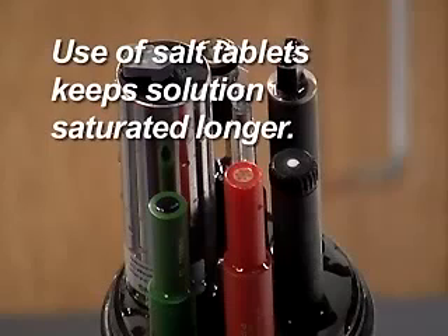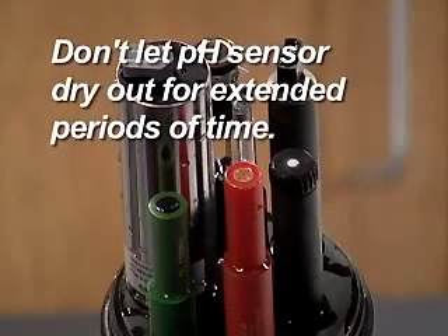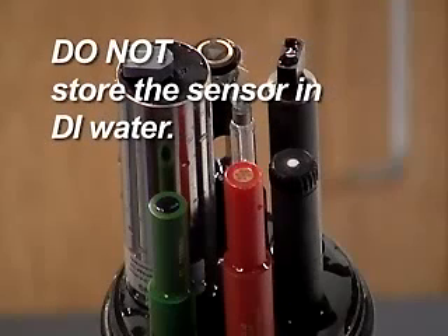Use of the salt tablets from the maintenance kit will keep the electrolyte solution saturated for longer periods of time. The pH sensor should not be allowed to dry out for extended periods. When not in use, store the sensor in pH 4 buffer or alternatively clean tap water. Do not store the sensor in deionized water or sample water. DI water will damage the sensor bulb, and the organisms in sample water will foul the bulb and junction.